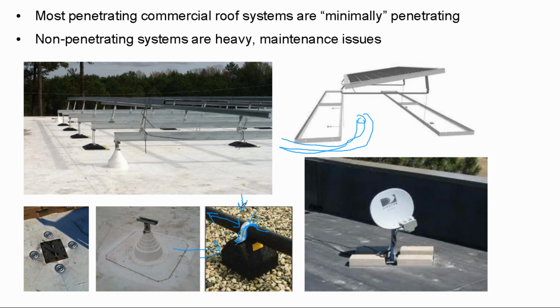And it's just not a good idea to have any section of these rails one way or the other or in conduit stretching more than 120 feet in a joined fashion unless there are expansion points built into it. And so code actually kind of takes care of some of these issues within the array itself. In commercial building code, there are requirements that say every 120 feet you need at least a 4-foot, but often an 8-foot walkway between subarray sections.